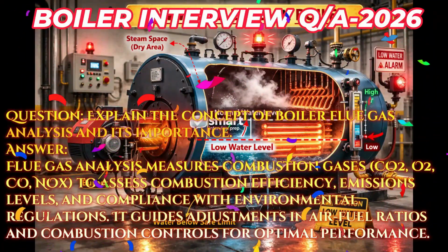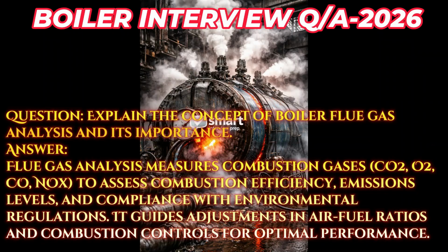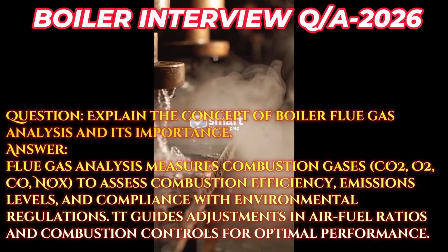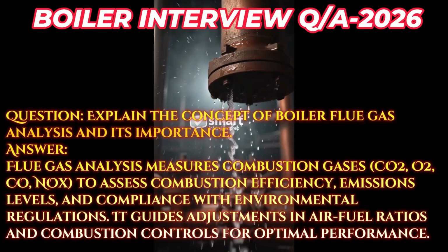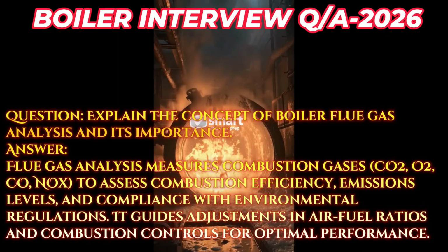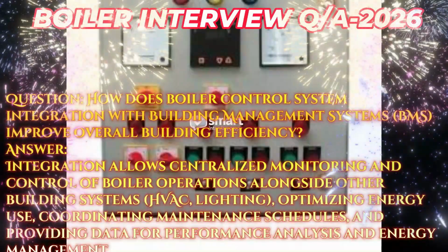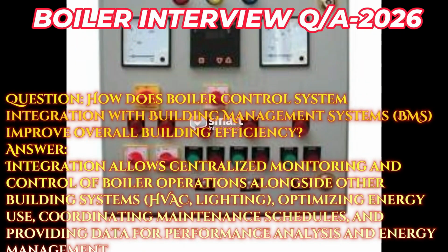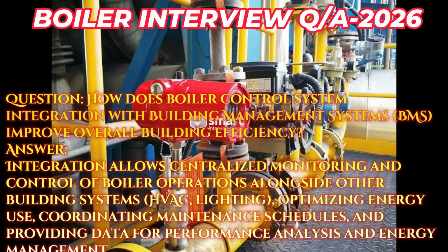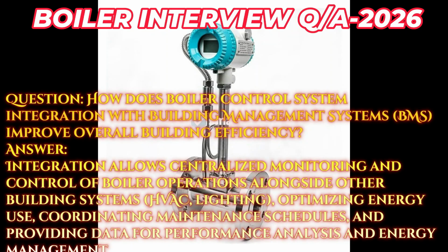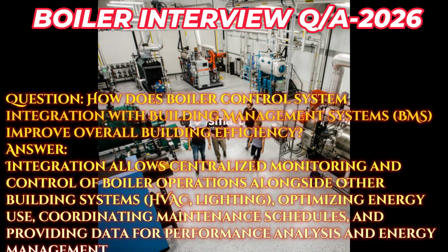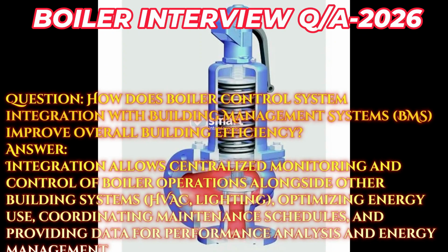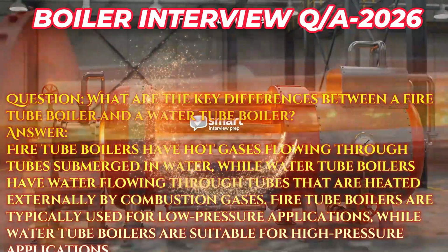Question: explain the concept of boiler flue gas analysis and its importance. Answer: flue gas analysis measures combustion gases, CO2, O2, CO, NOx, to assess combustion efficiency, emissions levels, and compliance with environmental regulations. It guides adjustments in air-fuel ratios and combustion controls for optimal performance. Question: how does boiler control system integration with building management systems, BMS, improve overall building efficiency? Answer: integration allows centralized monitoring and control of boiler operations alongside other building systems, HVAC, lighting, optimizing energy use, coordinating maintenance schedules, and providing data for performance analysis and energy management. Question: what are the key differences between a fire tube boiler and a water tube boiler?